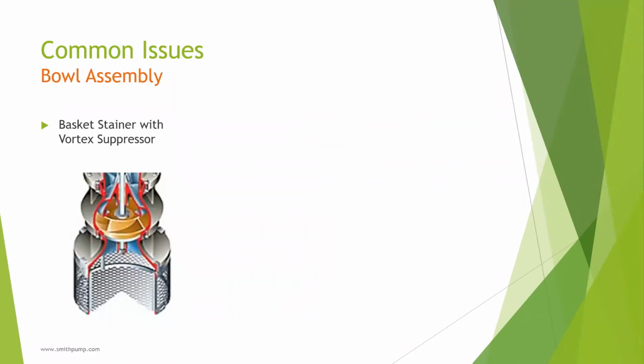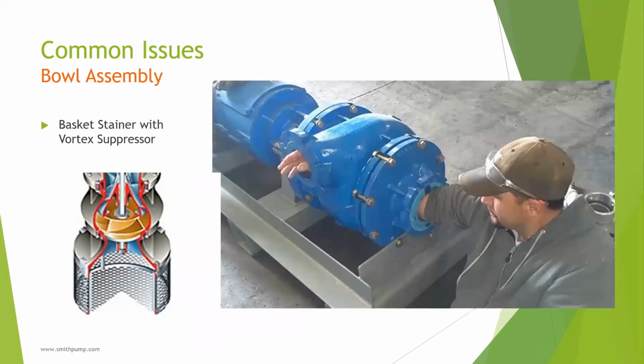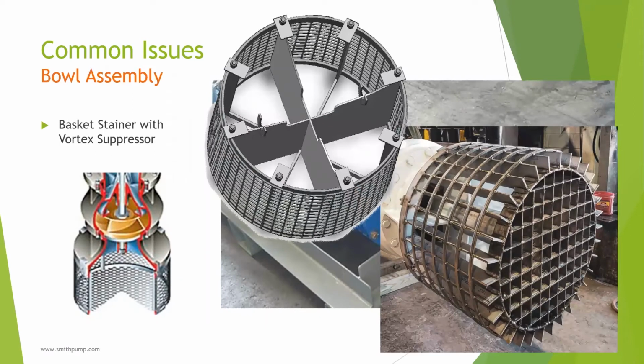So Smith Pump always recommends a basket strainer with the built-in vortex suppressor on all turbine pumps, whether barrel mounted or wet pit. They serve two purposes. One is to keep stuff out of the pump that doesn't belong, and the other is to reduce pre-swirl and help correct the fluid approach angle. So here are two examples using the plate baffles on the left and vane grating on the right. So always request a basket strainer with a built-in vortex suppressor made from stainless steel.